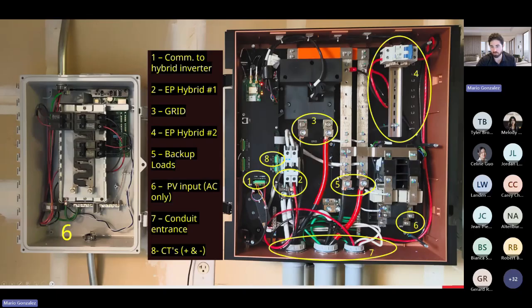Backup loads. Here you have your backup loads termination or connection points. And here you have your AC extension ports, AC input for AC only. It's on the second port, generator only on the first port. Actually, you can put AC on either port. The one that is only for one is the generator one, and that's extension port number 1. So if you have a site where they have a small AC string, I would recommend always using extension port number 2, just because if in the future the homeowner wants to install a generator, you don't have to worry about moving wires from one extension port to the other one. You just can hook it up to the extension port 1.